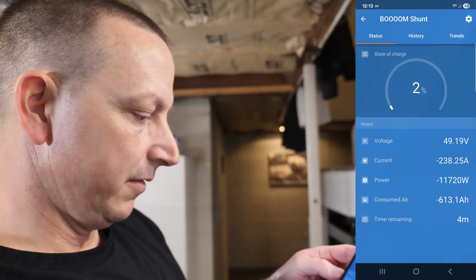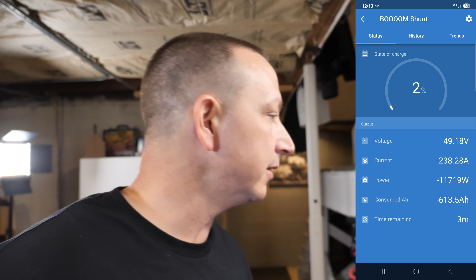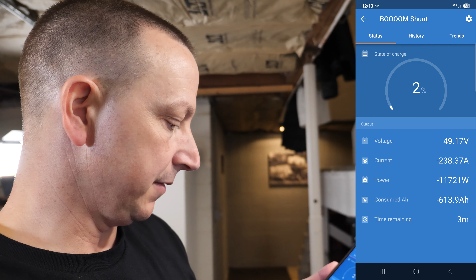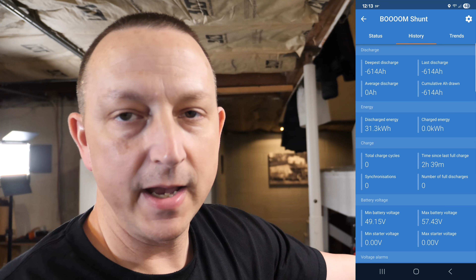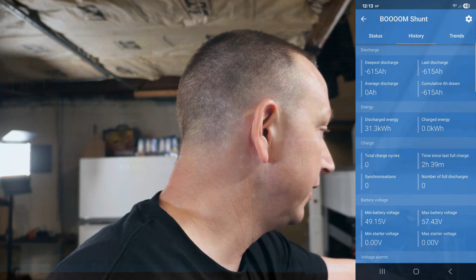8% left on there. I'm going to swap out the batteries on the camera so I don't miss the end. All right, boom shunt is showing 2% left. We're at 49.19 volts on here, 49.49 volts on the JK. So we have 3 minutes left at 2% on here, 614 amp hour, 31.3 kilowatt hour. And if we take a look at the JK software, we're at 3% state of charge, 49.39 volts, 248 amps, 12,260 watts coming out of the battery.